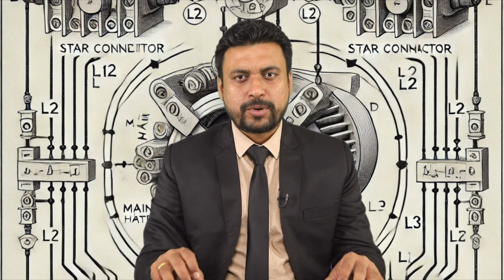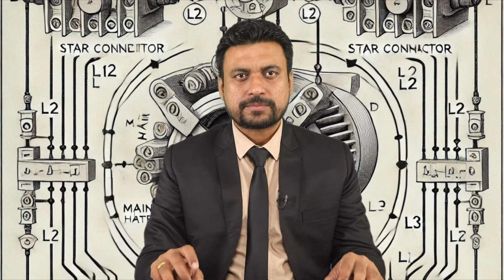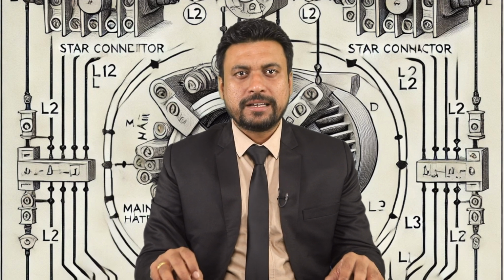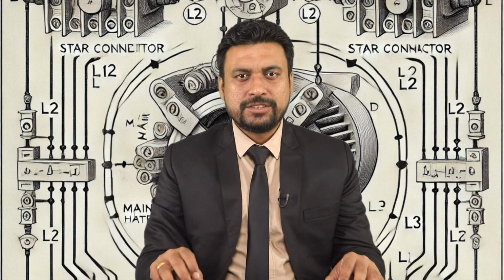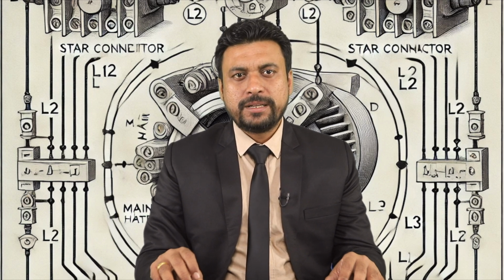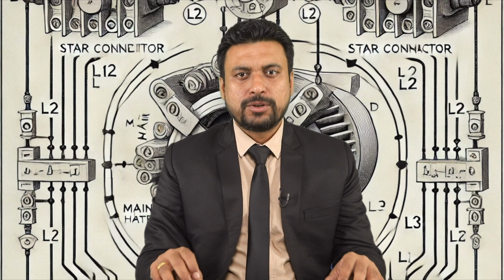Once the motor reaches approximately 80% of its full load speed, a timer or other control mechanism triggers the transition from the star configuration to the delta configuration. At this point, the motor windings are reconnected in a delta configuration, which allows each winding to receive the full line voltage. This change enables the motor to produce its full rated torque and run at its full speed. The transition from star to delta is usually seamless, although there is often a brief moment of reduced torque during the switch, which in most applications is not problematic.